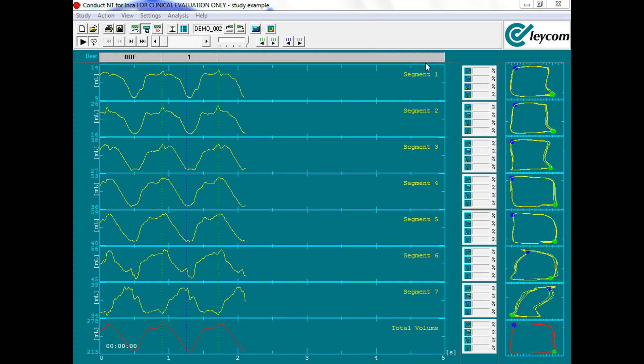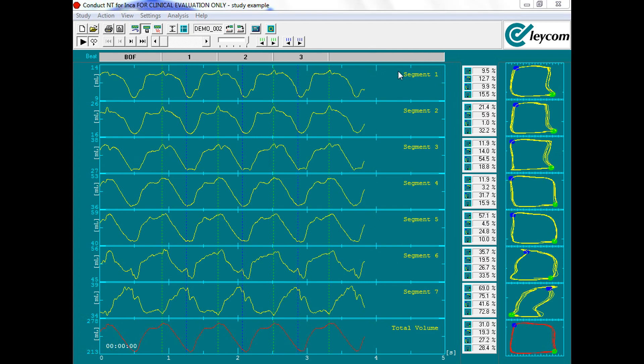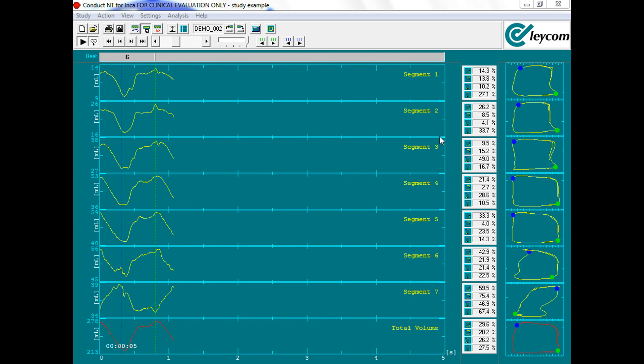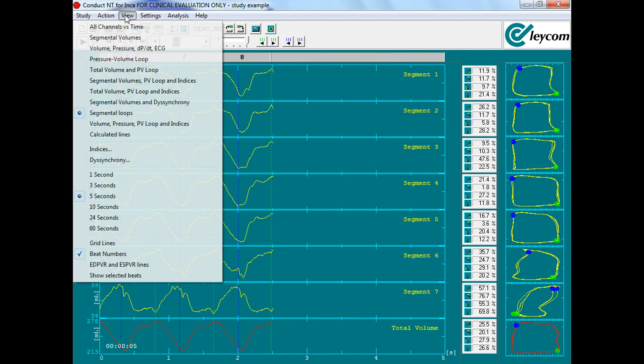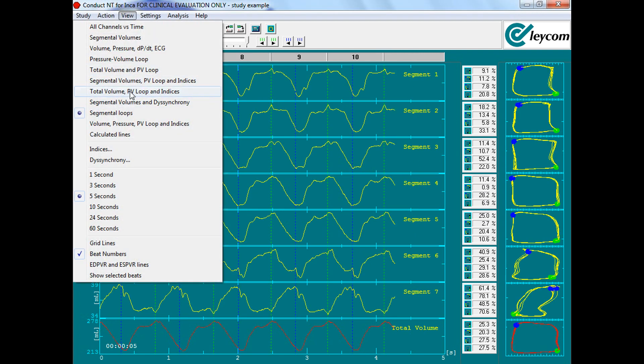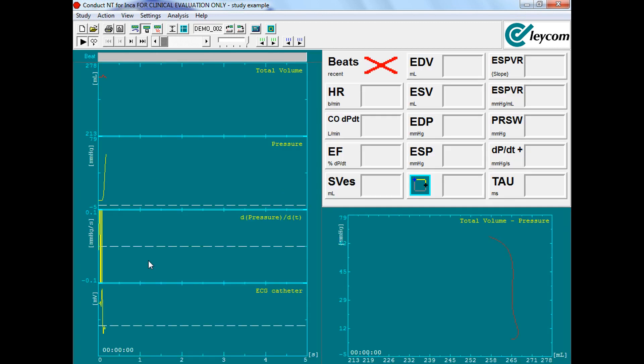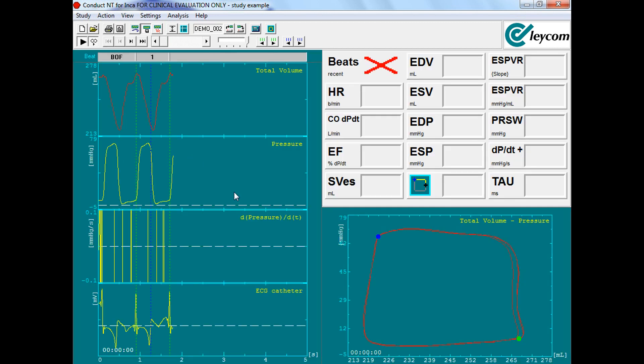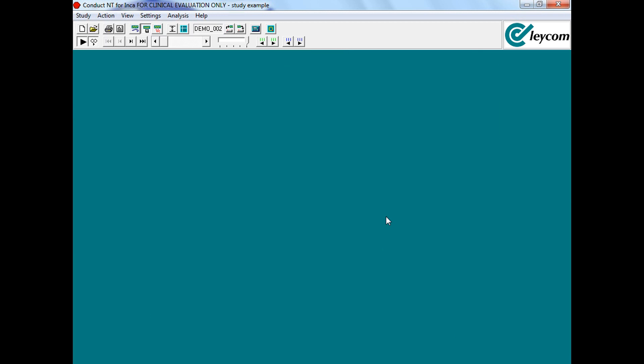Recall that segment 1 is closest to the apex. Also, the pressure sensor is located across segment 3. Thus, if a ventricular pressure signal is apparent, as we see here, an LV pressure, then one should expect a minimum of three segments being used. This is the case for any PV loop study regardless of LV or RV PV loop acquisition.